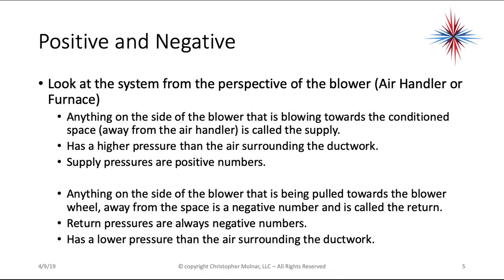We also have to look at the positives and negatives of air pressure. From the system perspective, you're at the blower in the air handler or furnace. Anything on the side of the blower that is blowing towards the conditioned space, away from the air handler or furnace, is called the supply. It has a higher pressure than the air surrounding the ductwork — supply pressures are always positive numbers. Anything on the side of the blower being pulled towards it is called the return, and return pressures always have a negative number. The supply being positive and the return being negative makes sense because we want to pull the air in as a vacuum and push the air out of the supply.